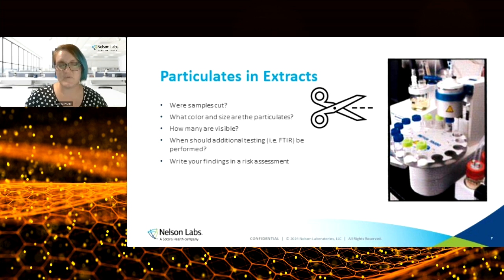One of the first questions I ask sponsors or the lab when we're investigating this is, were the samples cut, and is this the potential source of those particulates? When you see particulates, ask yourself several questions to help identify the possible source. The color and the size can help you identify that source. Also, depending on the amount visible, you can tell whether it is of concern. If it's just a few black particulates and you have a black plastic component that was cut, it's pretty clear where those particulates came from, and that it's not clinically relevant because your device isn't normally cut during clinical use. Then you have that conversation in a risk assessment.